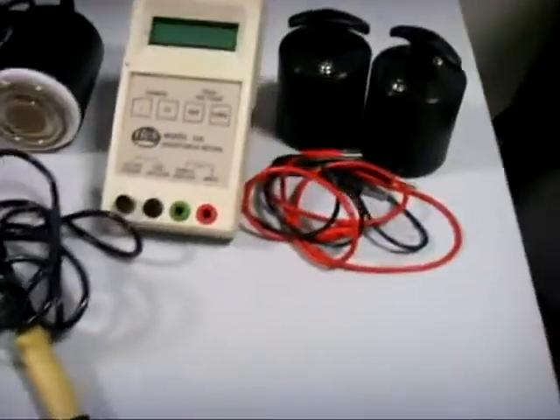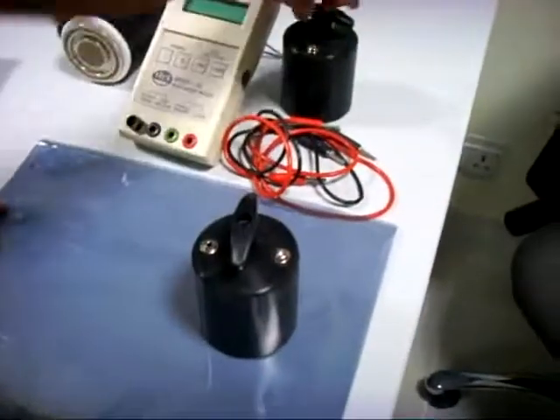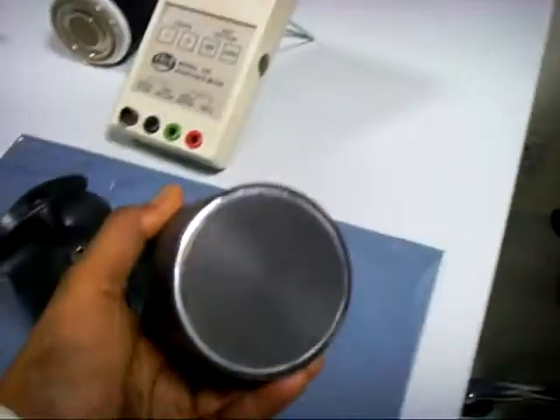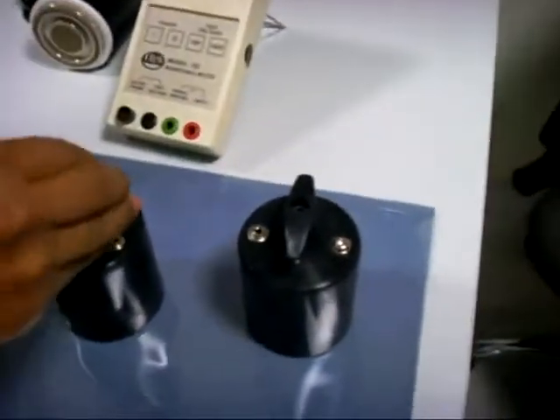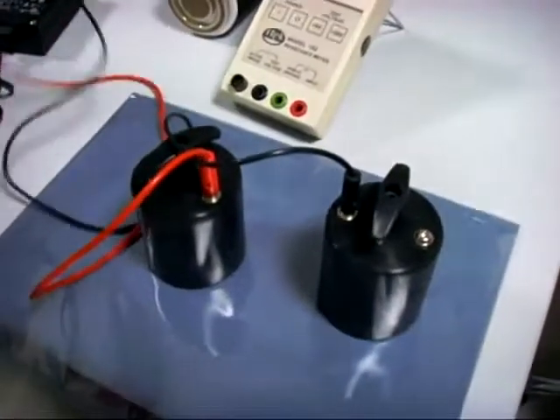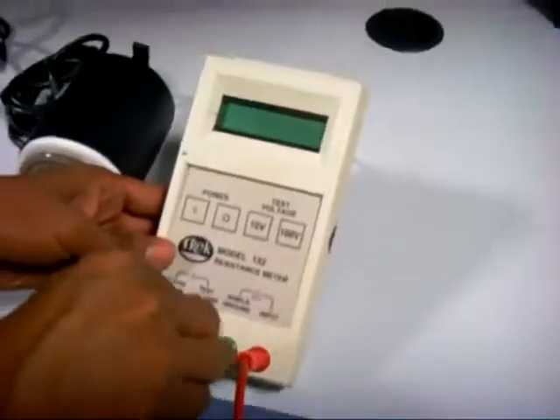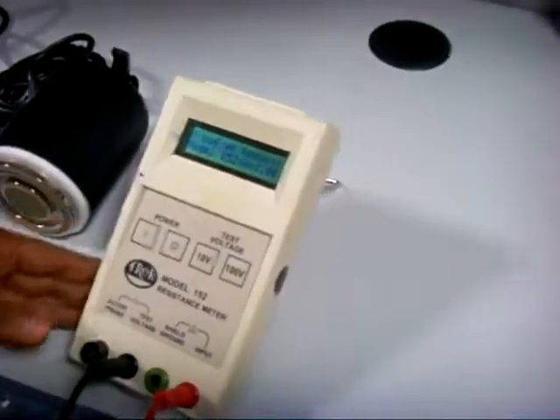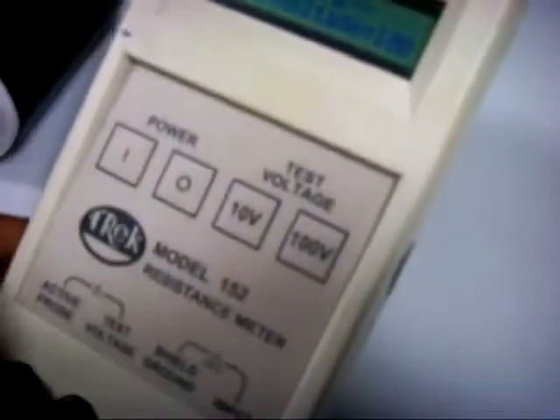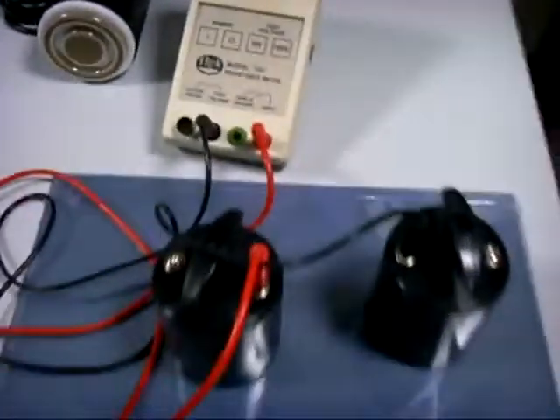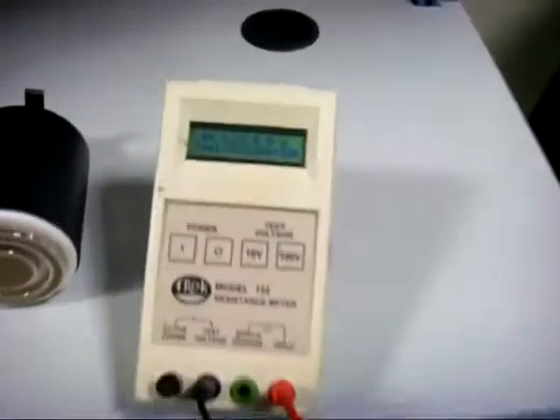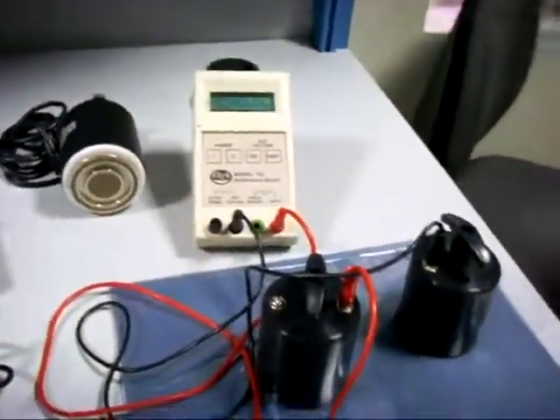Now we are checking the point-to-point resistance of the static shielding bag by using the point-to-point probe. These are 5-pound electrodes with conductive rubber based electrodes as per US standard. Now we are checking the point-to-point surface resistance of the TSS bag. We are checking at the 100 volt range. We are getting 1.9 into 10 power 9 ohms. This is the point-to-point surface resistance.